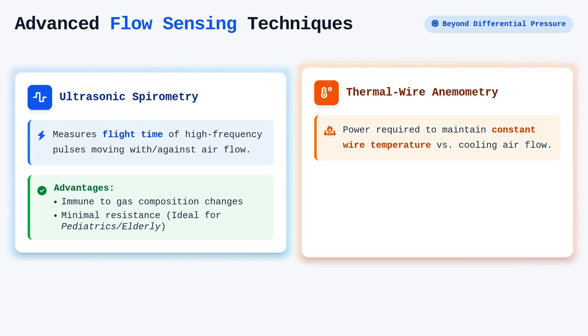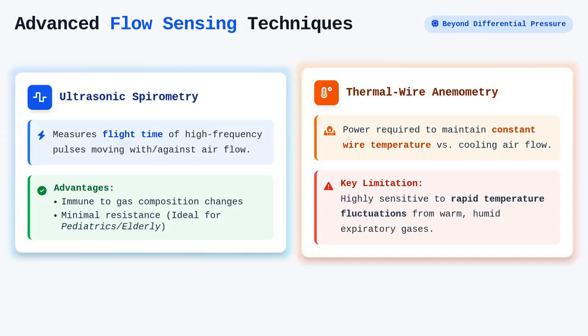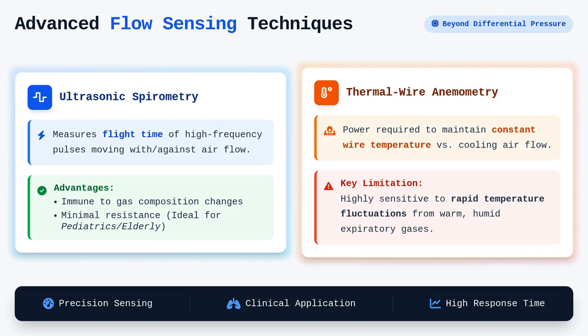Thermal wire anemometry uses a heated wire maintained at a constant temperature. The flow of air cools the wire, and the power required to keep the temperature constant serves as a measure of the flow rate. While these sensors offer excellent response times, they can be sensitive to rapid temperature fluctuations that are inherent in the delivery of warm, humidified expiratory gases from the lung.